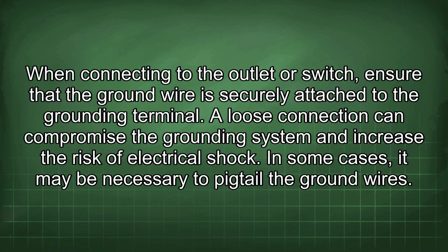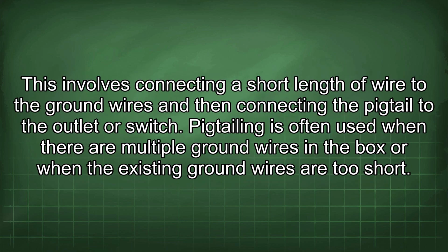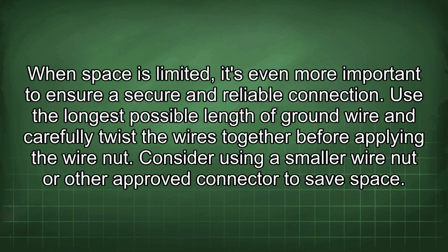In some cases, it may be necessary to pigtail the ground wires. This involves connecting a short length of wire to the ground wires and then connecting the pigtail to the outlet or switch. Pigtailing is often used when there are multiple ground wires in the box or when the existing ground wires are too short. When space is limited, it's even more important to ensure a secure and reliable connection. Use the longest possible length of ground wire and carefully twist the wires together before applying the wire nut. Consider using a smaller wire nut or other approved connector to save space.